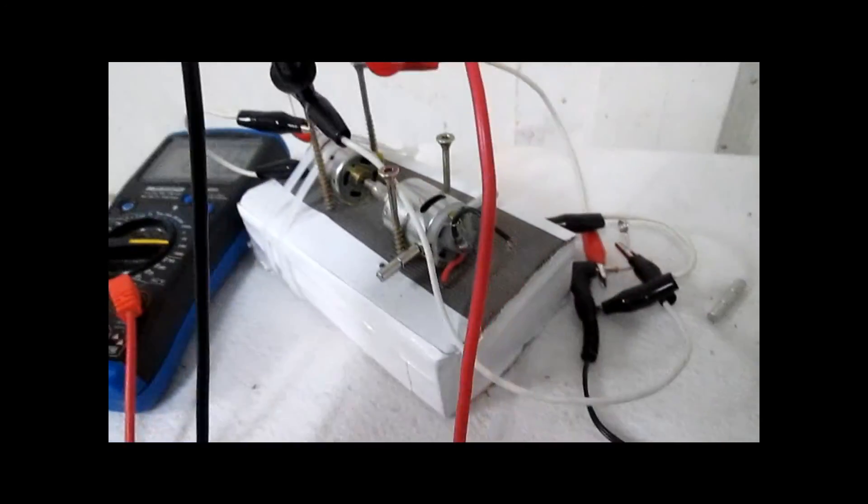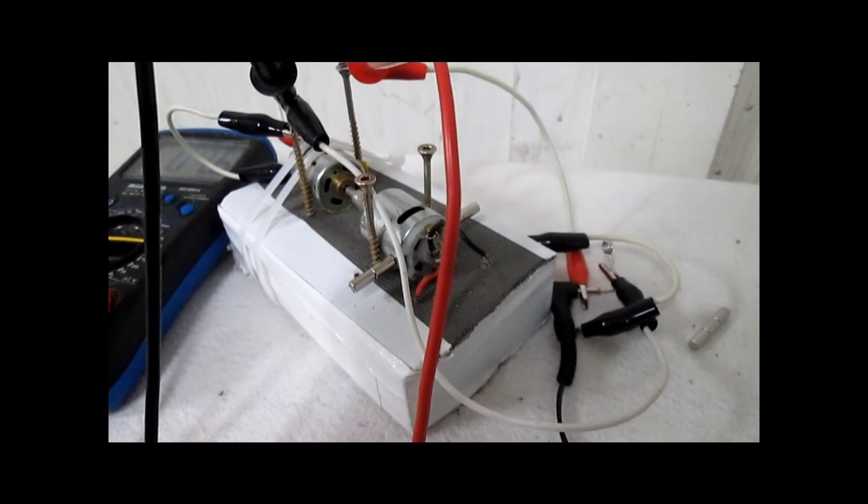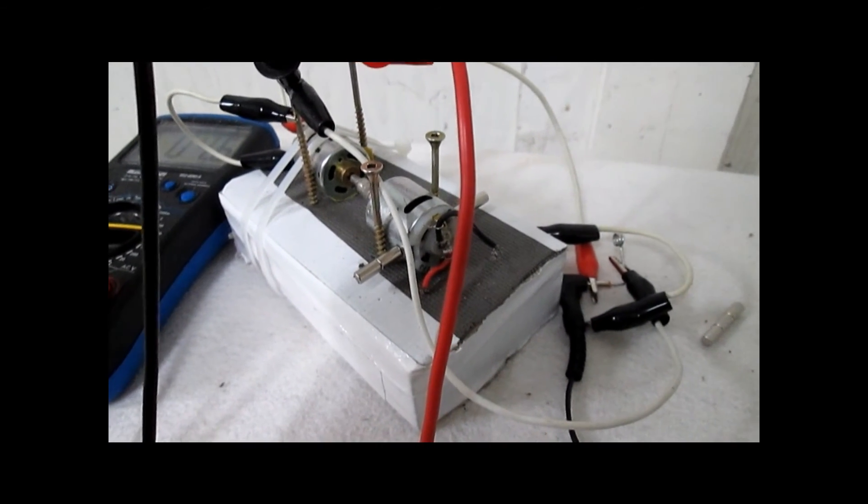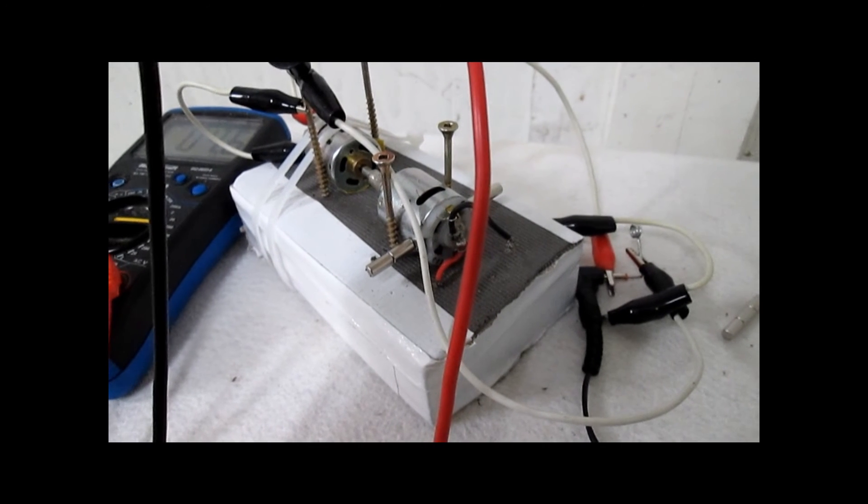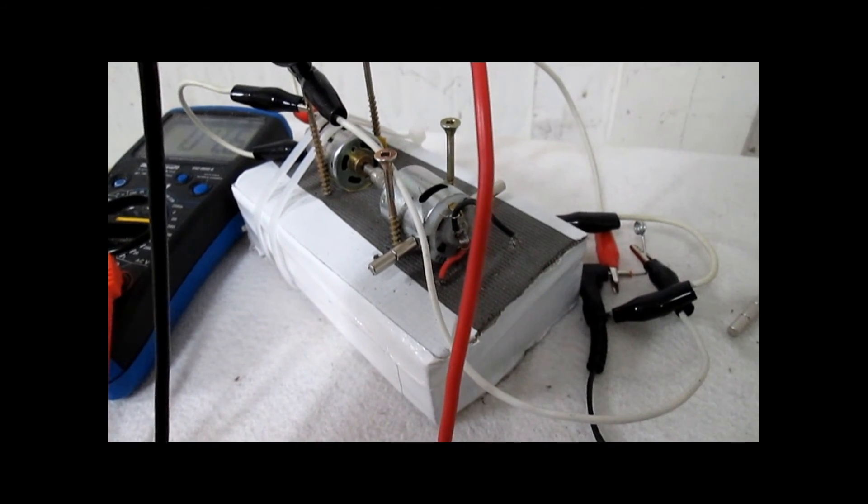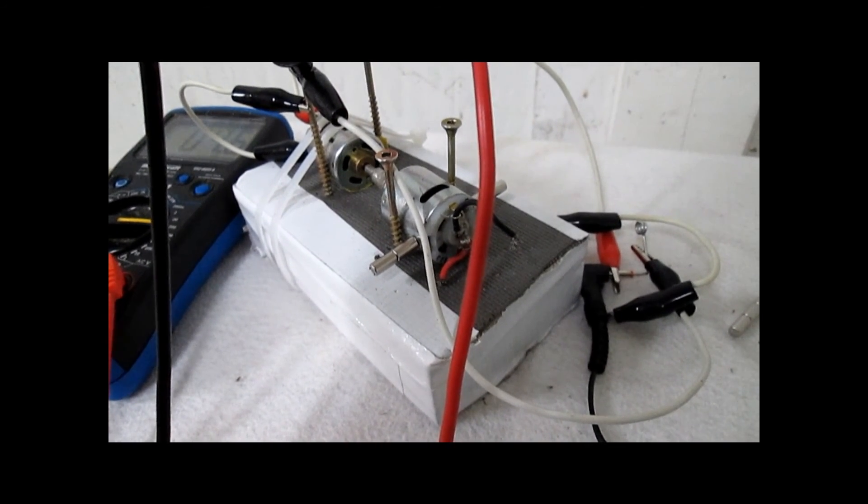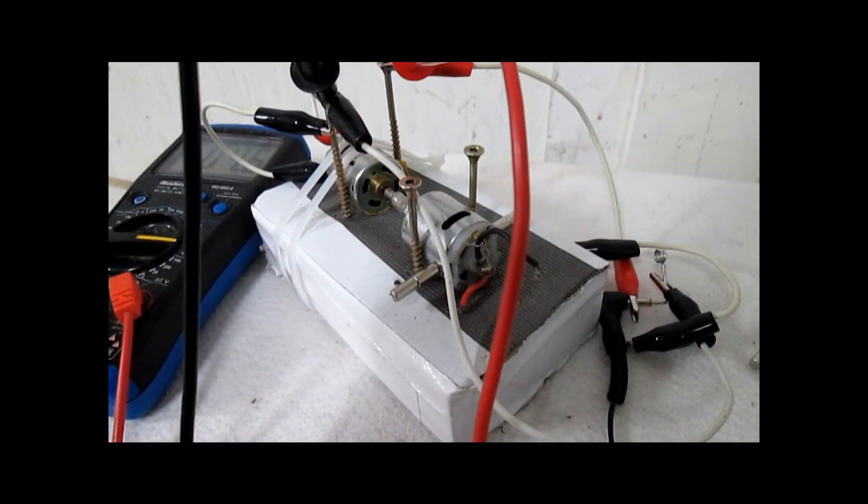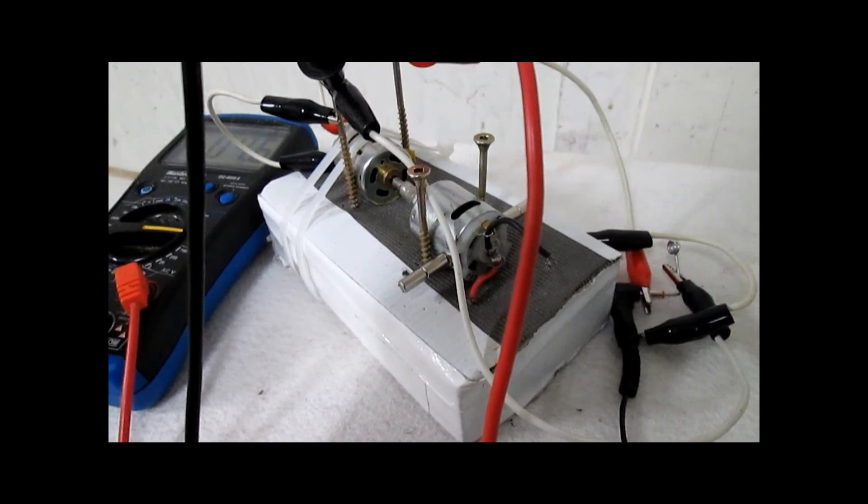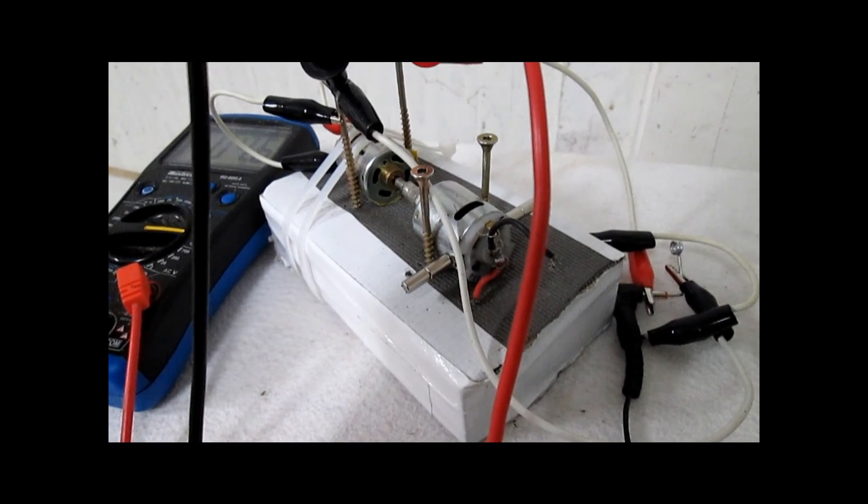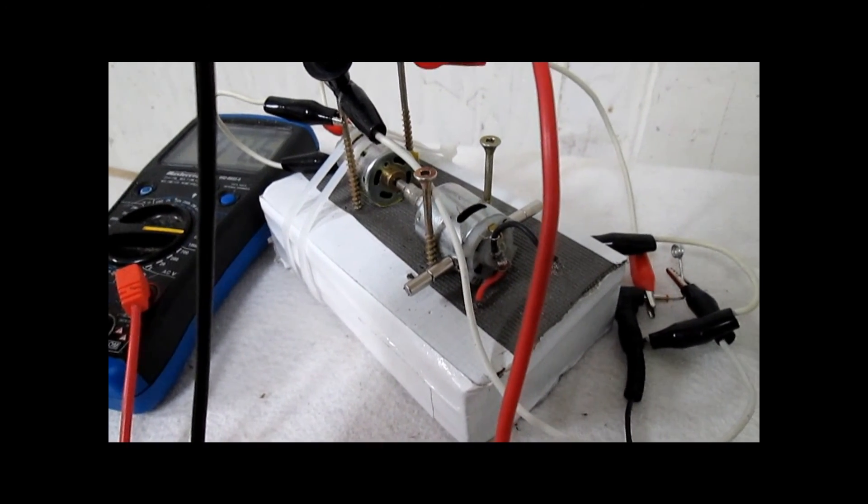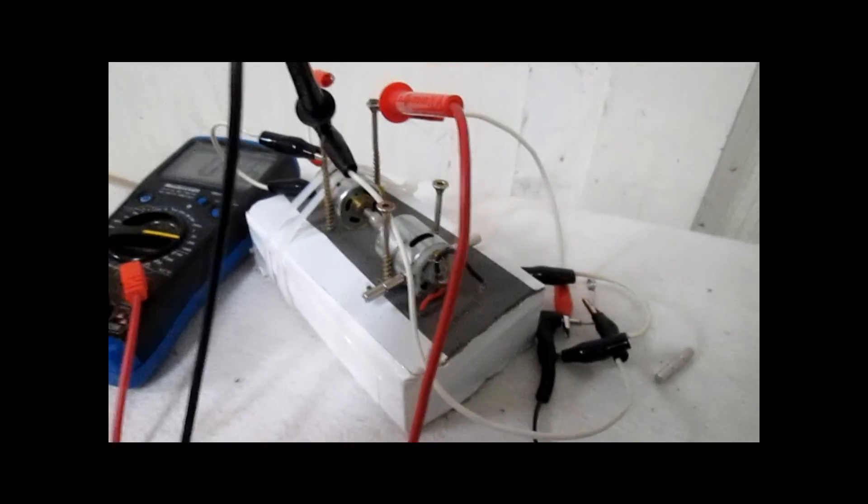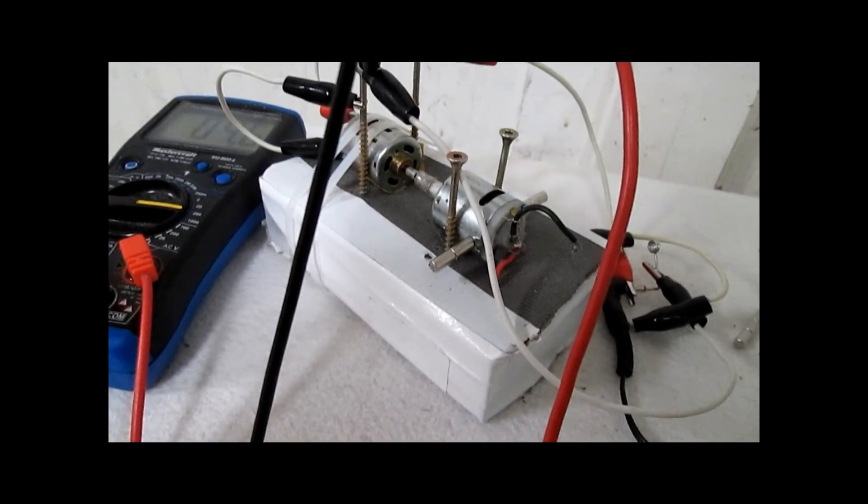So now I have to test the amperage, because theoretically, these should not be more than 80% efficient. 75% to 80% for this type of motor. And for, say, an appliance motor that's AC, even lower, 60% to 70%. Why? Because if they're electrically excited, they actually use power.